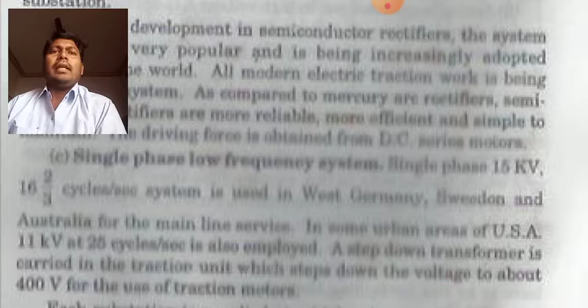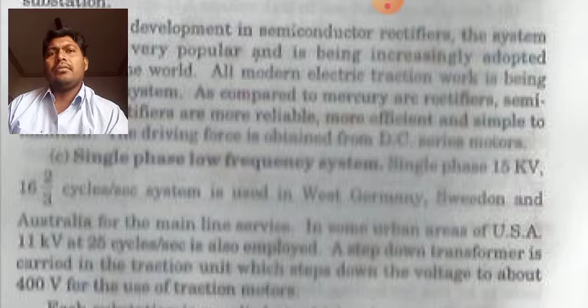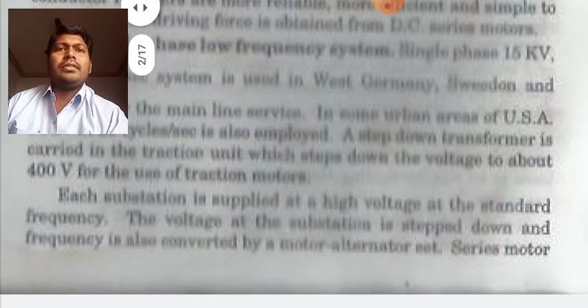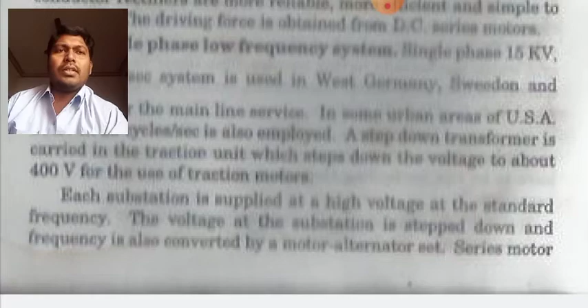In some urban areas of United States of America, 11 kV at 25 Hz is also employed. A step down transformer is carried in the traction unit, which steps down the voltage to about 400 volt for the use of traction motors. Each substation is supplied at a high voltage at a standard frequency. The voltage at the substation is stepped down and frequency is also converted by a motor alternator set.